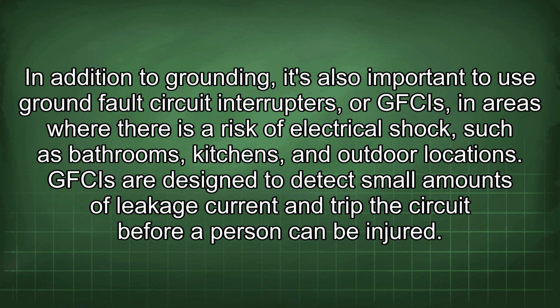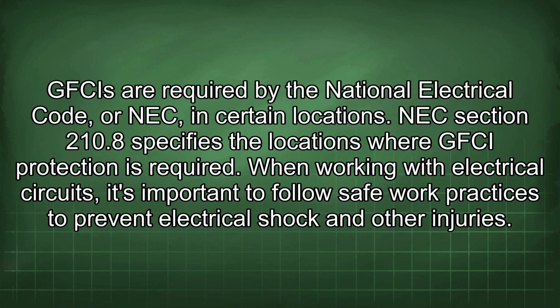In addition to grounding, it's also important to use ground fault circuit interrupters, or GFCIs, in areas where there is a risk of electrical shock, such as bathrooms, kitchens, and outdoor locations. GFCIs are designed to detect small amounts of leakage current and trip the circuit before a person can be injured. GFCIs are required by the National Electrical Code, or NEC, in certain locations. NEC Section 210.8 specifies the locations where GFCI protection is required.